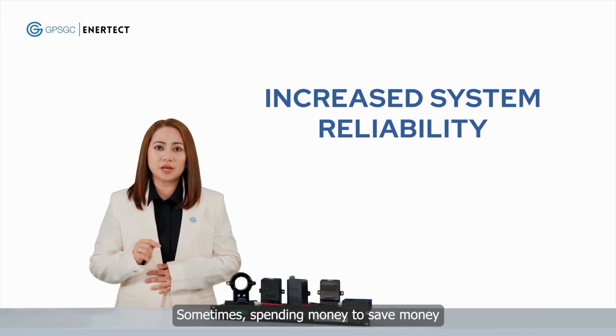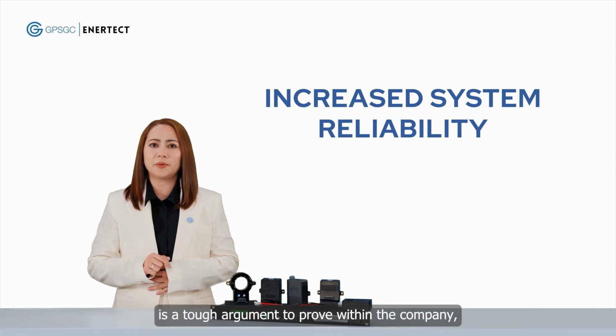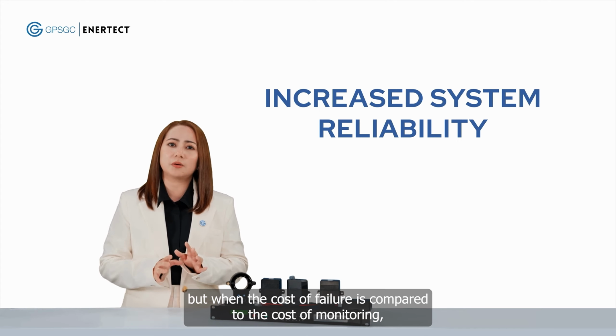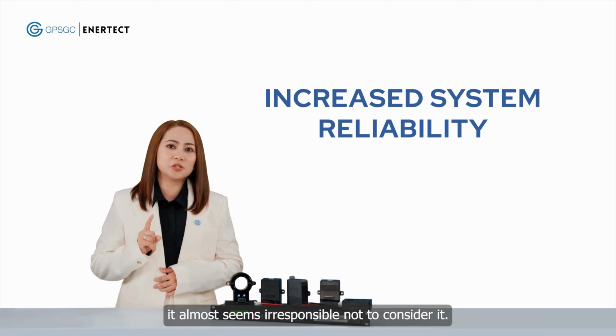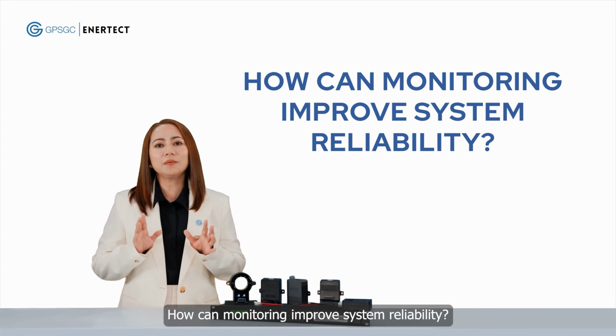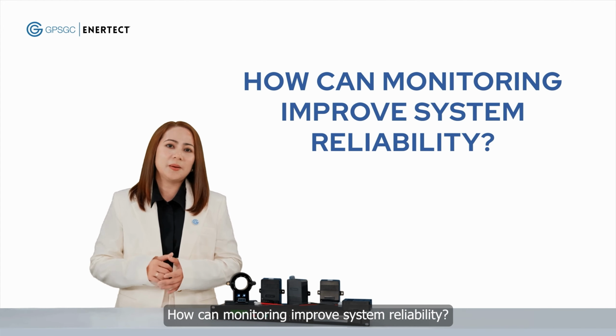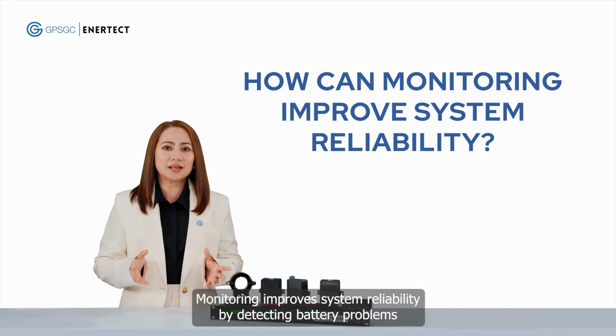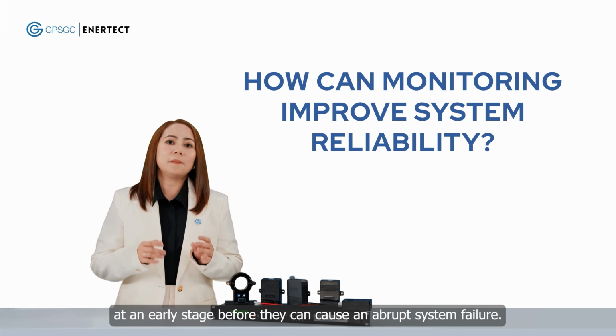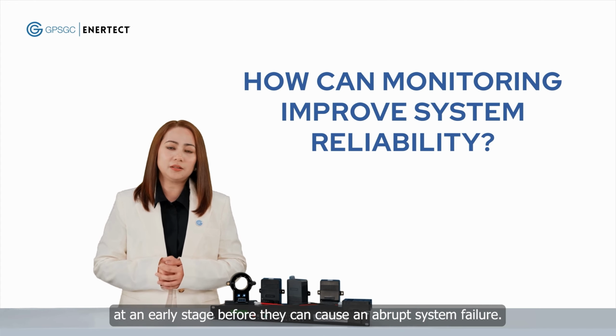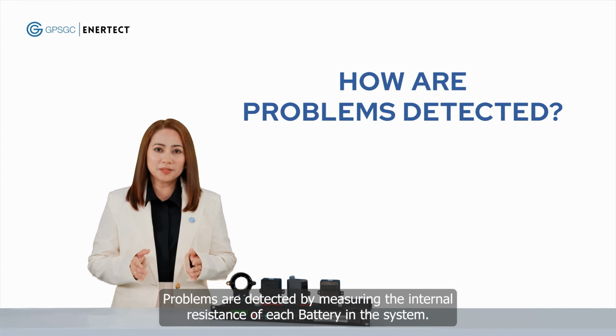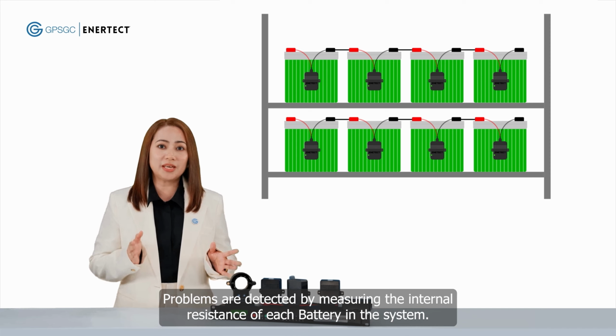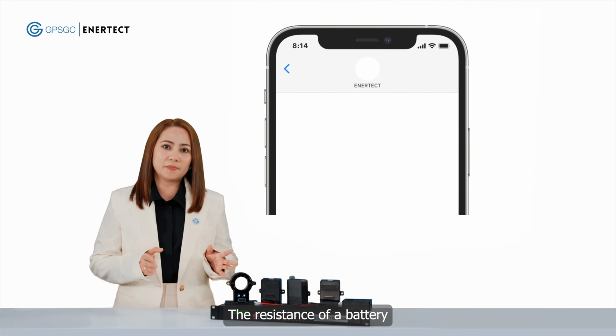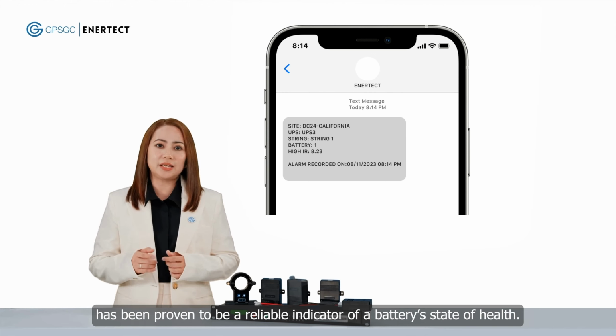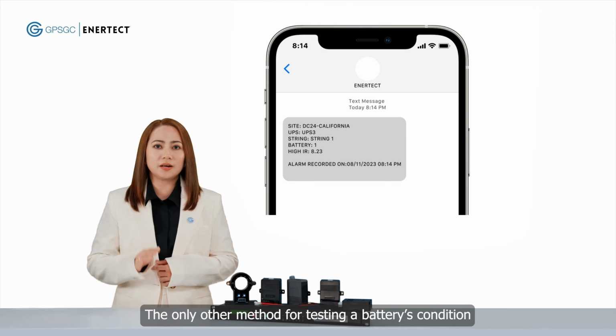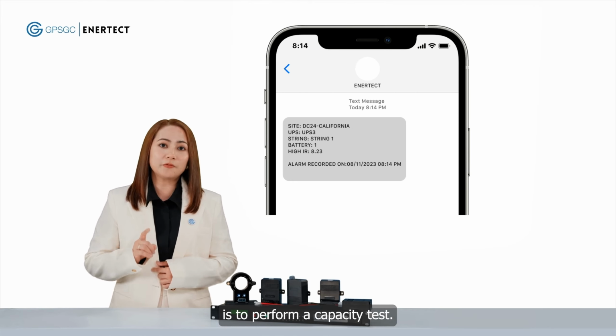Sometimes, spending money to save money is a tough argument to prove within the company. But when the cost of failure is compared to the cost of monitoring, it almost seems irresponsible not to consider it. How can monitoring improve system reliability? Monitoring improves system reliability by detecting battery problems at an early stage before they can cause an abrupt system failure. How are problems detected? Problems are detected by measuring the internal resistance of each battery in the system. The resistance of a battery has been proven to be a reliable indicator of a battery's state of health. The only other method for testing a battery's condition is to perform a capacity test.